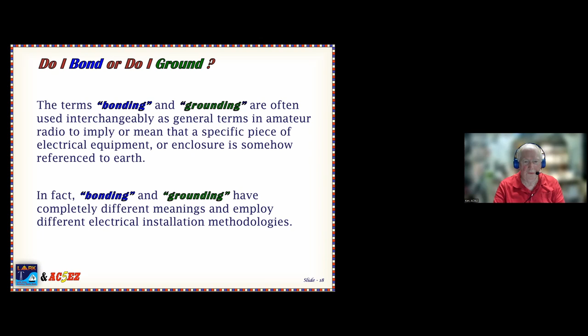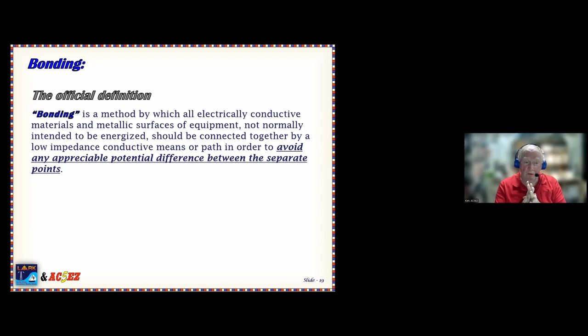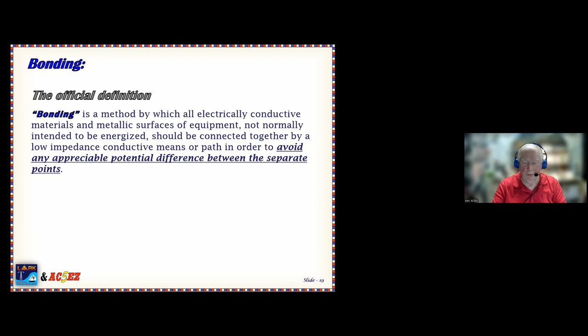Let's take bonding. The official NEC definition: bonding is a method by which all electrically conductive metallic materials and surfaces — like your transmitter or amplifier chassis — not normally intended to be energized, should be connected together by a low impedance conductive means, such as a wire or braided strap, to avoid any appreciable potential difference. In other words, don't get shocked if you touch your transmitter and then your amplifier. They should all be at the same potential.